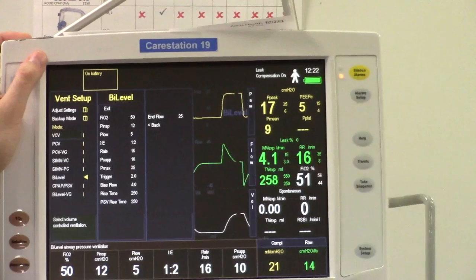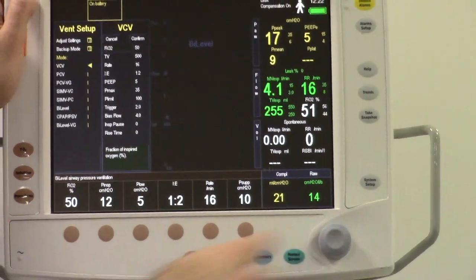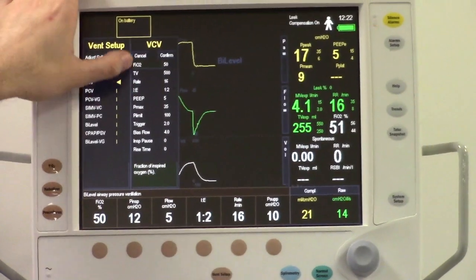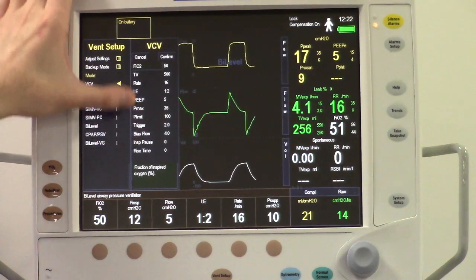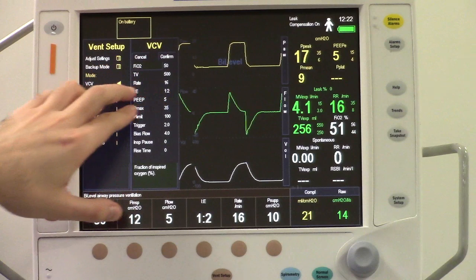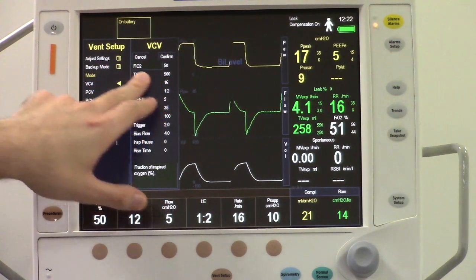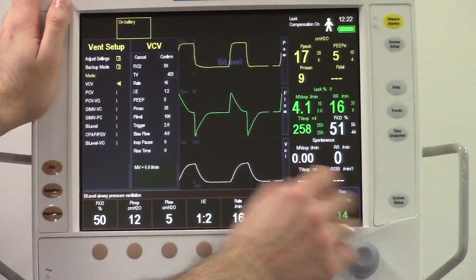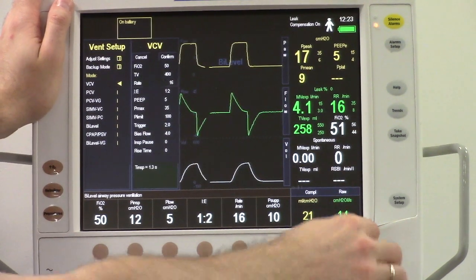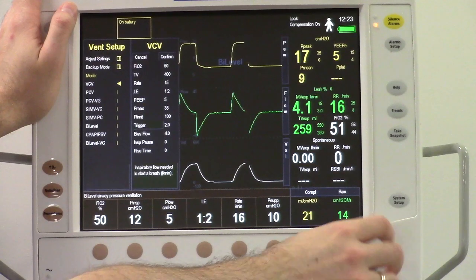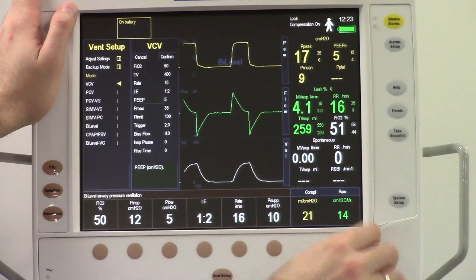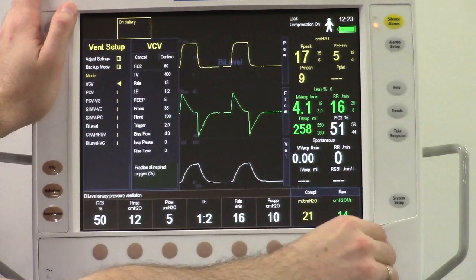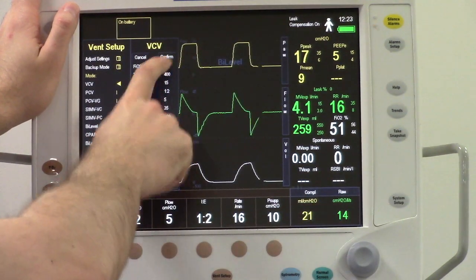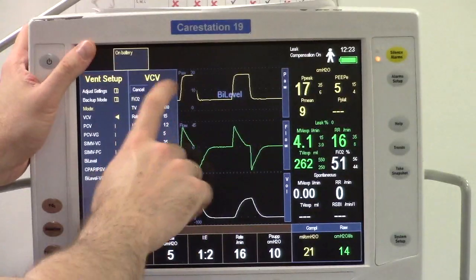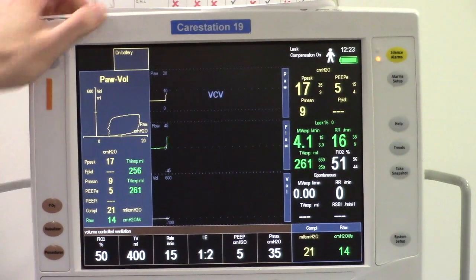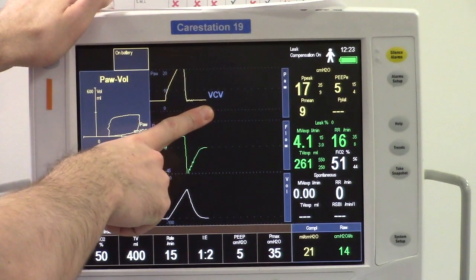So the ventilator will do the whole work for the patient. Yeah. So we've selected the mode, but we need to select the parameters as well. Yeah. So oxygenation, tidal volume, and so on. Let's say we want a tidal volume of 400. Yeah. Respiration rate of 15. And we're going to leave the rest as it is. So now we just need to confirm. You navigate with this knob until you see the green highlight on the button over there. Yeah. So you press confirm, and we are in volume control now.